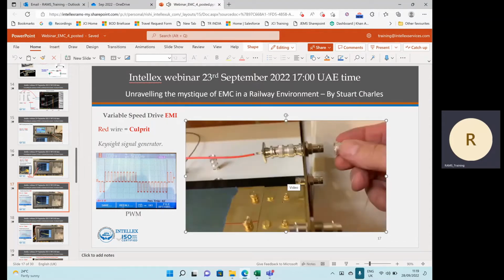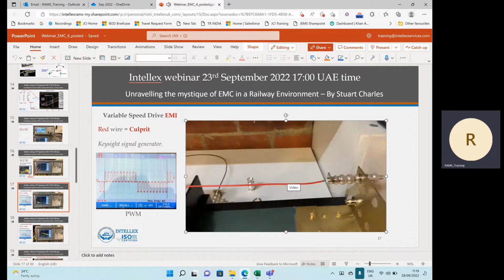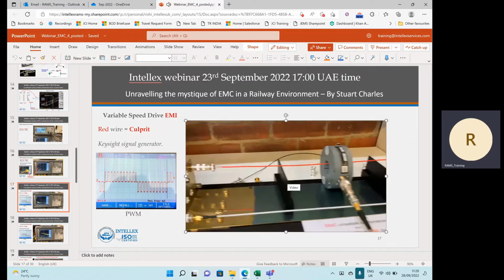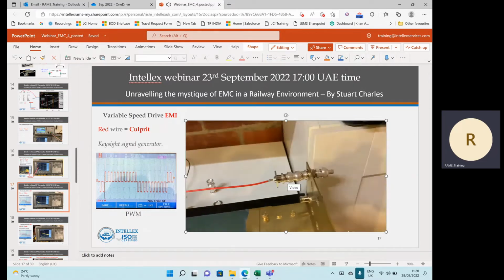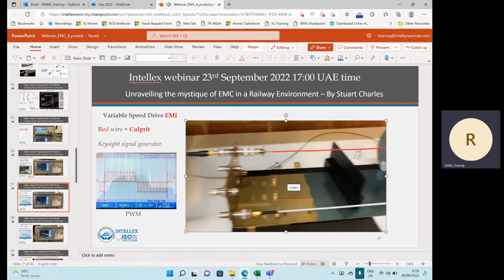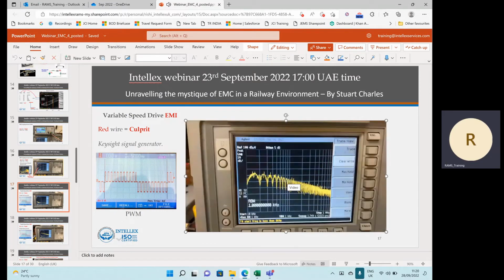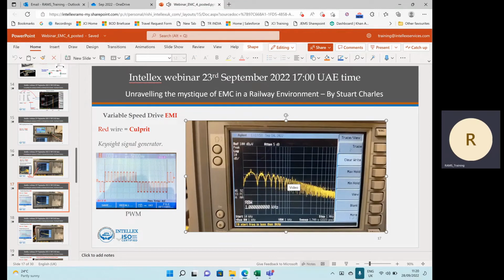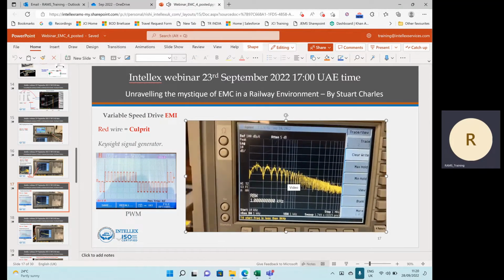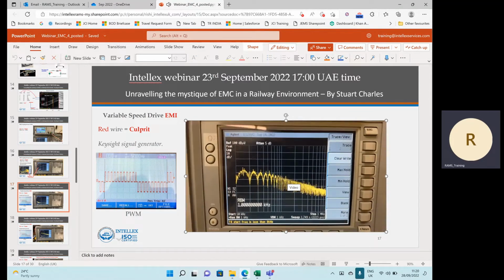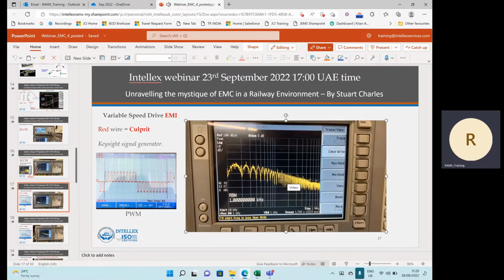So let's put our 50 ohm load onto the cable. We should now see some current because it's going down the red lead through the 50 ohm termination back to the ground plane. Let's take a look - and indeed there is our spectrum of current passing through from the VSD simulated output to a variable speed fan.